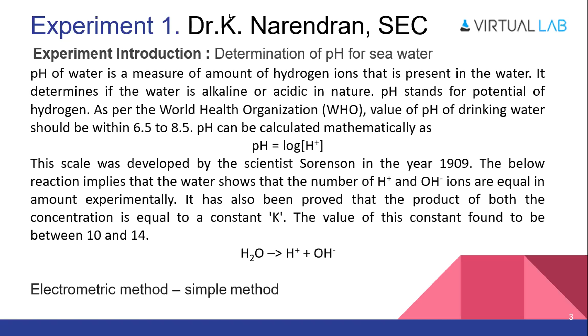So here we provided the electrodes for determining the pH, and we have a pH meter. The method is very simple. First, standardize the instrument with a buffer solution of pH 4. Then check again with a buffer solution of pH 7. The buffer is used to maintain a constant pH.